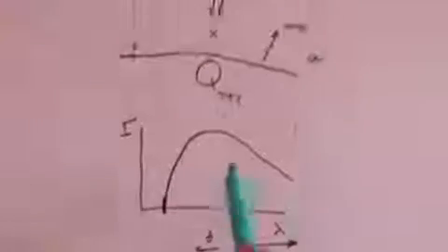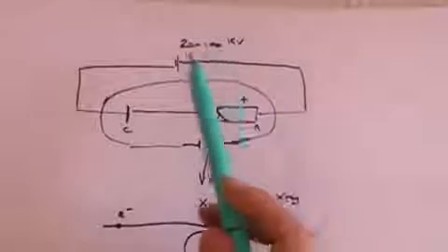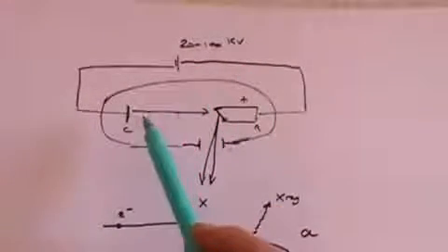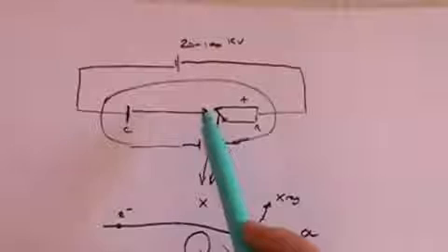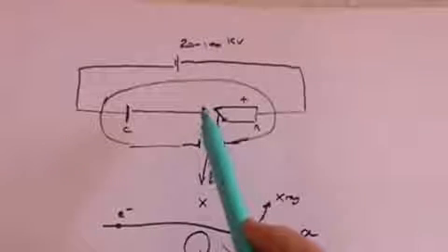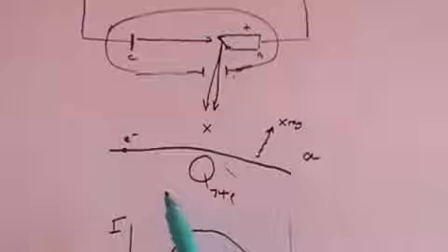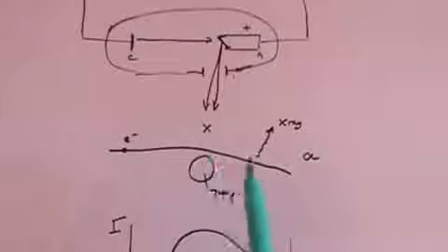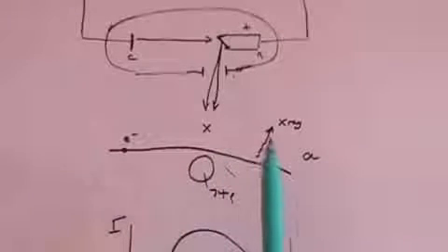Now the electron will have a maximum energy. That energy will be given by this voltage here. So the electrons that are coming across here will have energies of between 20 and 100 keV, kilo electron volts. And that energy, or some of that energy, as the electron slows down, is going to be given up into X-rays. Now there's a limit.